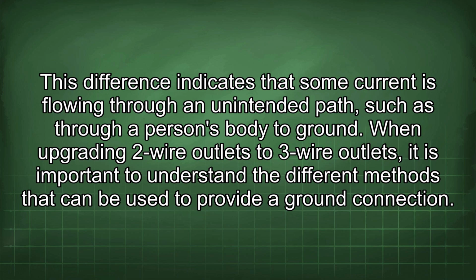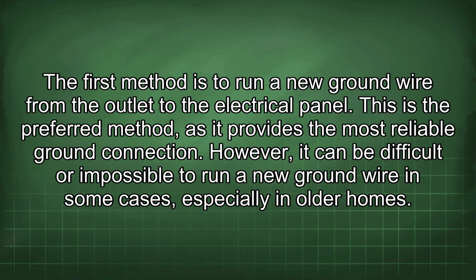When upgrading 2-wire outlets to 3-wire outlets, it is important to understand the different methods that can be used to provide a ground connection. The first method is to run a new ground wire from the outlet to the electrical panel. This is the preferred method as it provides the most reliable ground connection. However, it can be difficult or impossible to run a new ground wire in some cases, especially in older homes.